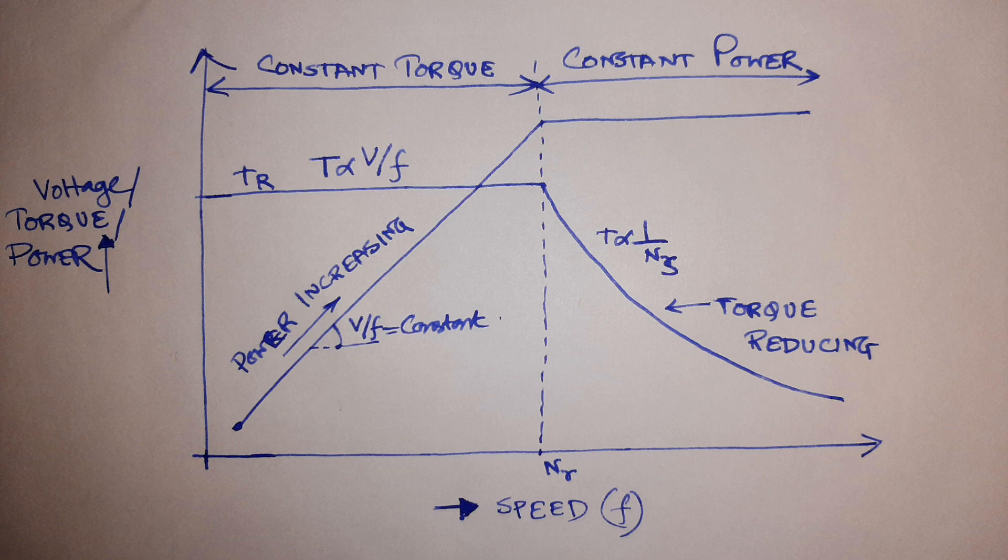In that region we have to keep the V/f constant, voltage by frequency ratio constant. Now torque is also equal to V/f, so in this region as the V/f is kept constant, the torque is also constant. Constant torque is delivered.